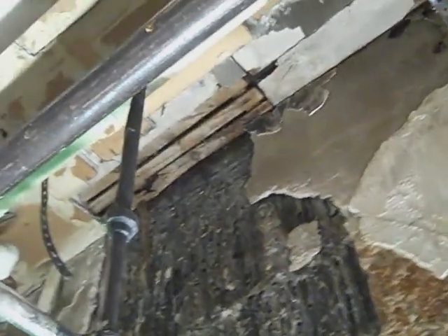Just going along that seam along the top, I don't know that you can see, but there are cobwebs up here. This should be sealed. Coming down, there's a hole here that leaks, and behind these doors there are also penetrations in the wall that are leaking. I'll see with the infrared camera, but this might have been caused by moisture. That takes a 2-foot left turn and vents outside.